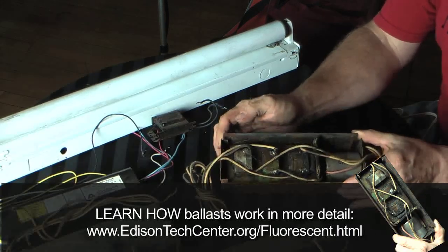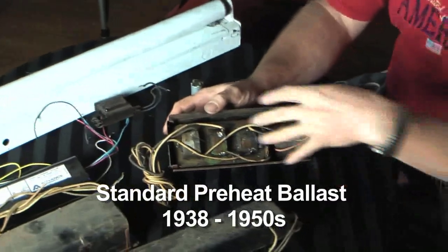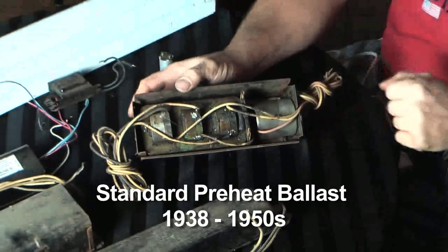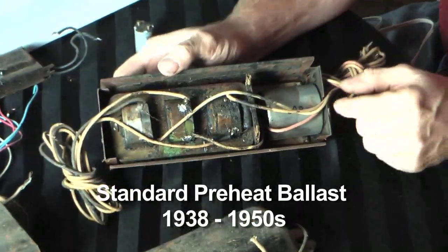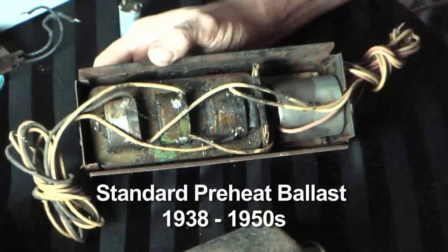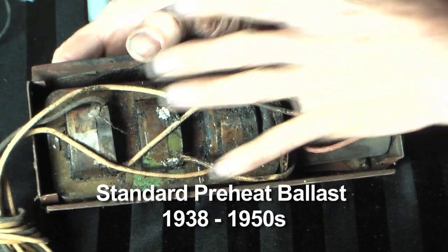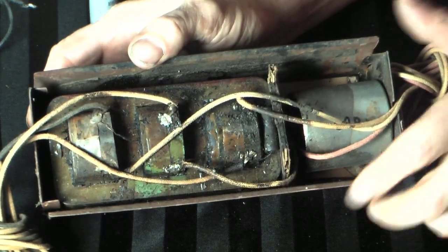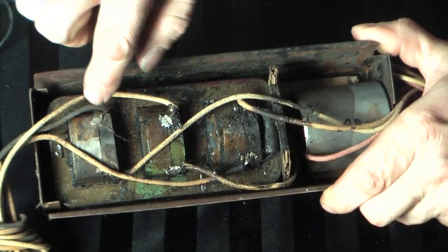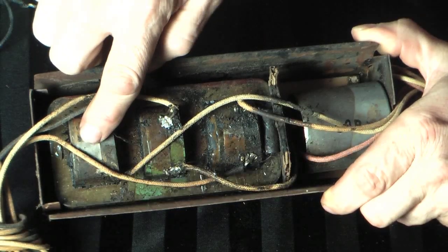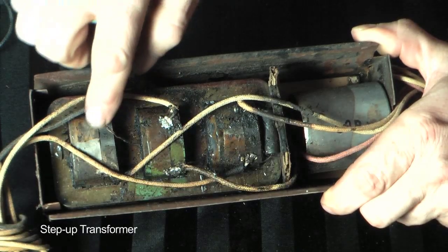Here we have a ballast, this one is from the 1940s, that I took all the tar out of because ballasts are filled with tar to make them run quieter and also to help dissipate heat. And this model is to run two 4 foot 40 watt lamps. And you can see what all is inside of a typical fluorescent ballast. Here is your transformer section. You've got a step up transformer on here which steps 120 volts up to about 200 volts, actually about 216 volts to supply enough voltage to run the lamps.